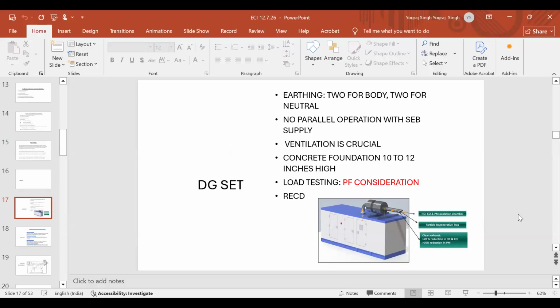Now, any DG set or transformer will require 4 earthings, 2 for body, 2 for neutral. One important thing is the distance of the earths from each other and from the building. From the building, any earth should be at least 4 feet away, and two adjacent earthings should not be less than 8 feet apart. So why is this condition there? As I had told you, the fault current energy tries to dissipate horizontally into the ground. If two earthings are close by, then there will be a short circuit between the two earthings.